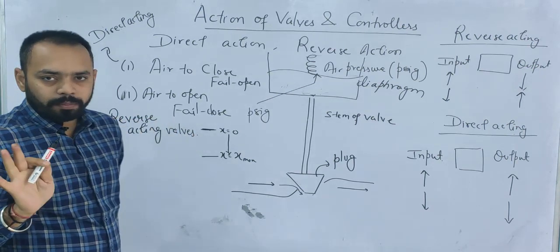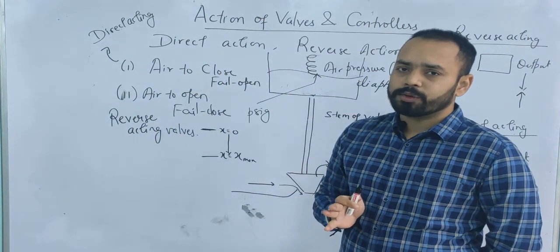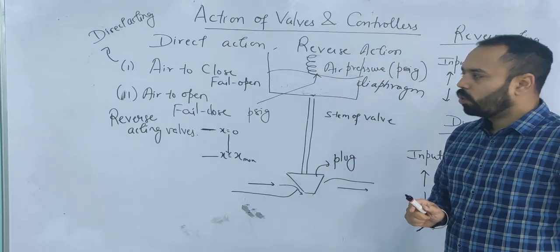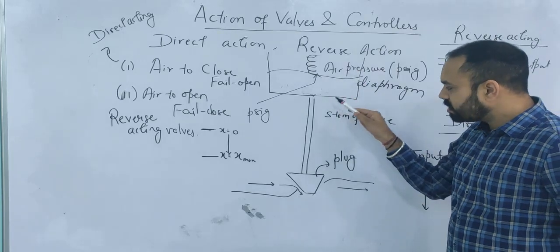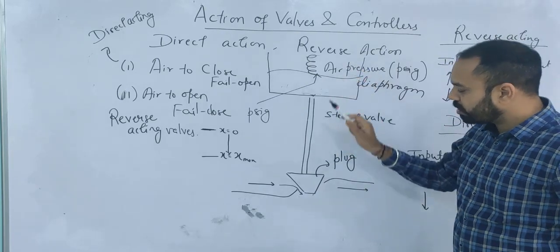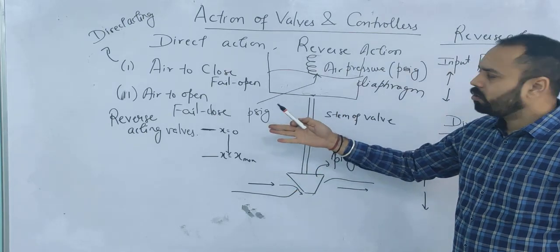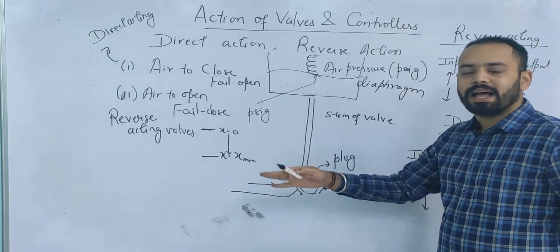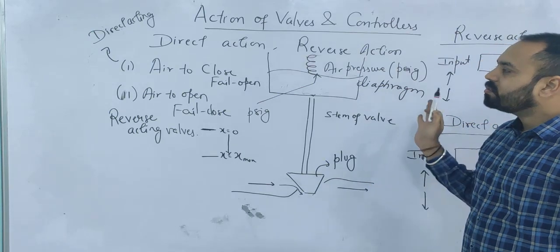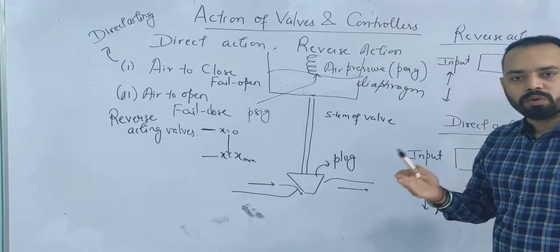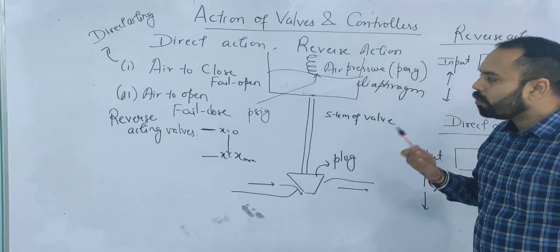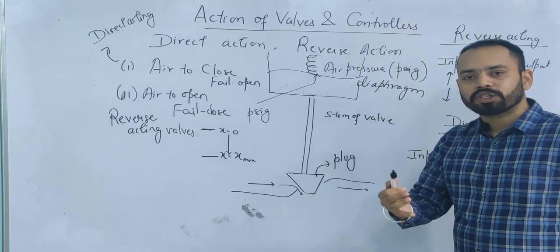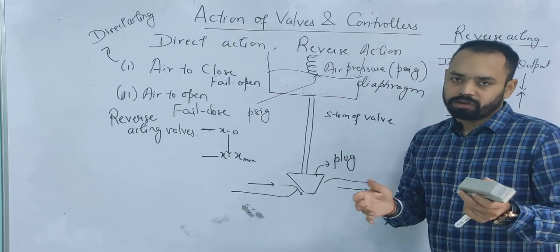This concept is not explained in most books, but there are questions in GATE examinations based on it. The action of the valve is calculated on the basis of air pressure and stem movement — not on the basis of air pressure and flow rate. In the air-to-close valve, increasing air pressure does decrease flow rate, but this is not the basis for defining the action of the valve. So: air-to-close is always direct acting, and air-to-open is always reverse acting.